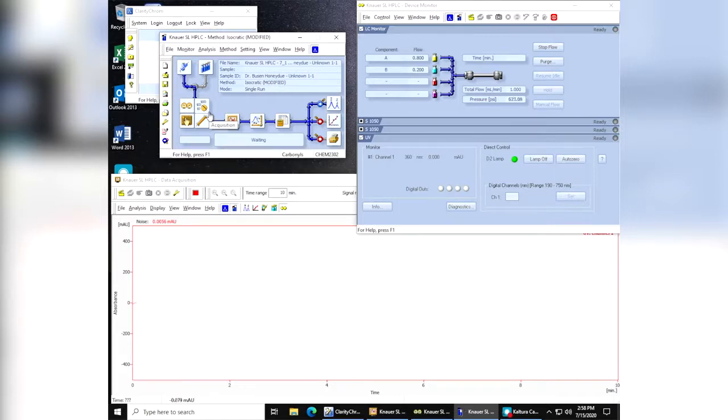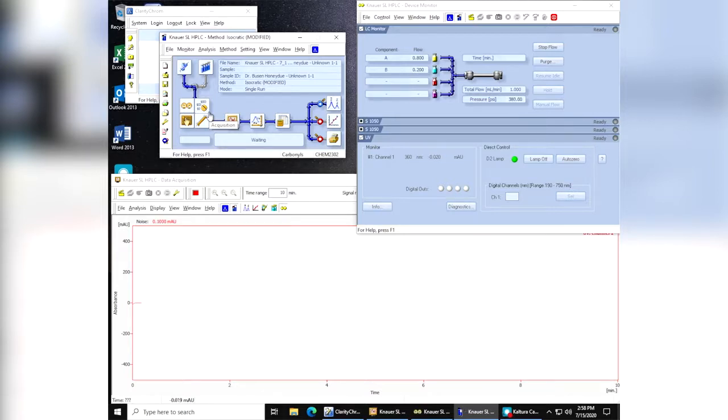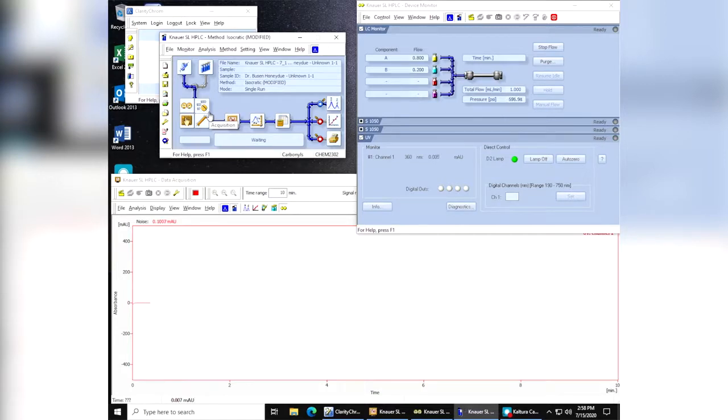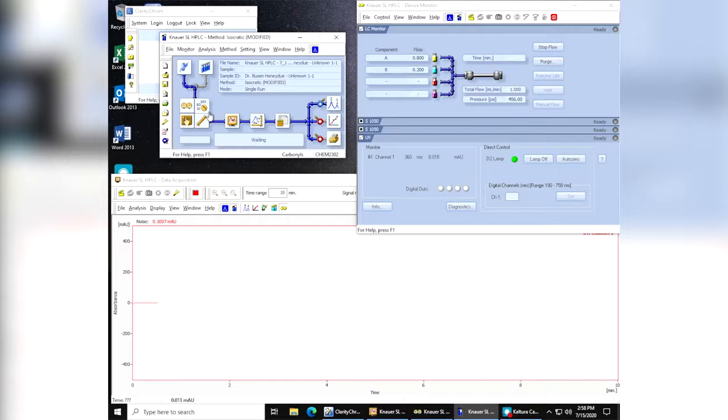We'll just need to wait a few minutes to allow the system to reach an equilibrium before we can actually do an injection. A lot of the times when you come to the instrument for an experiment, it will already be set up in terms of your first run, so you don't have to wait. But if you have to change the parameters of the program during the course of your experiments, then every time you change it you're going to have to wait three to five minutes to allow the system to reach a new equilibrium.